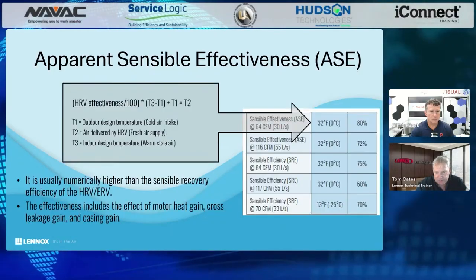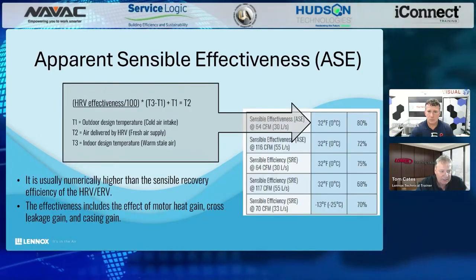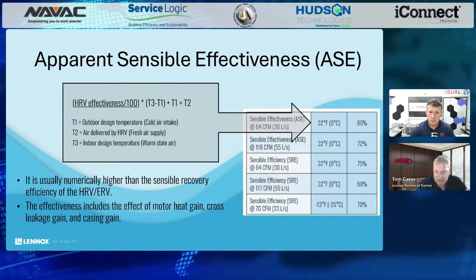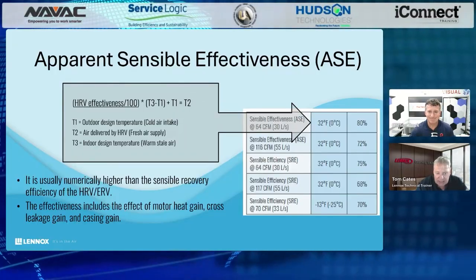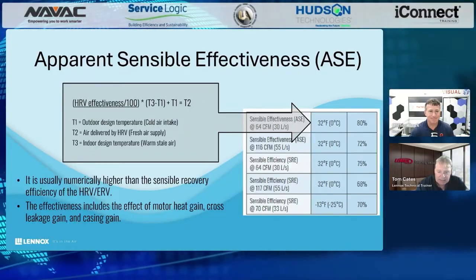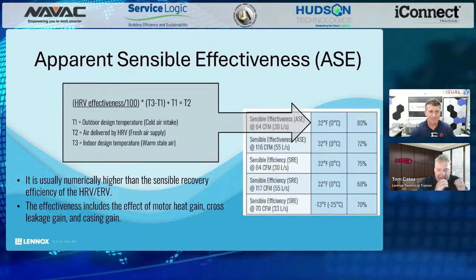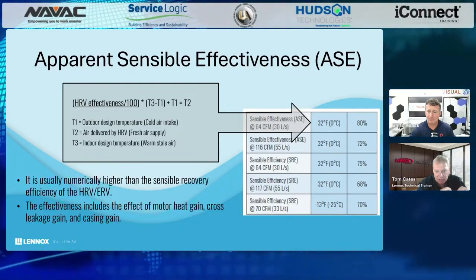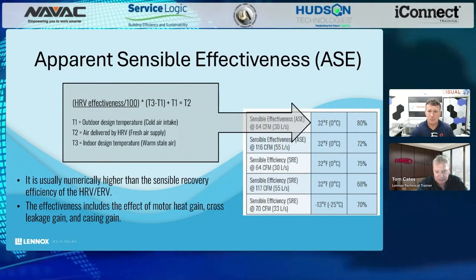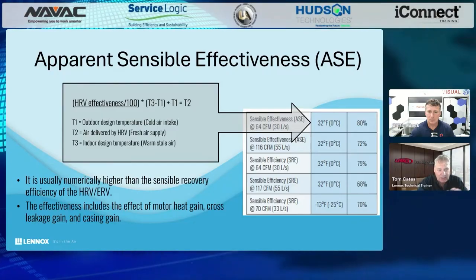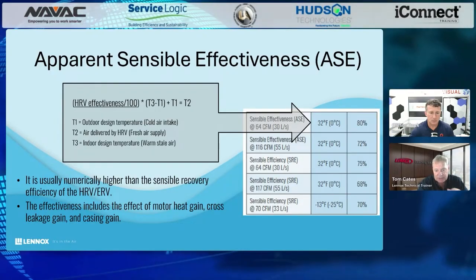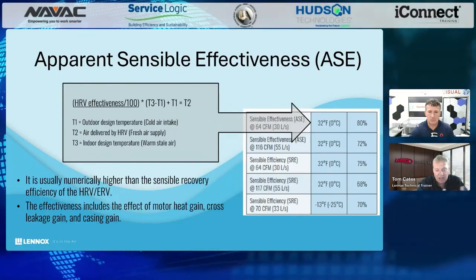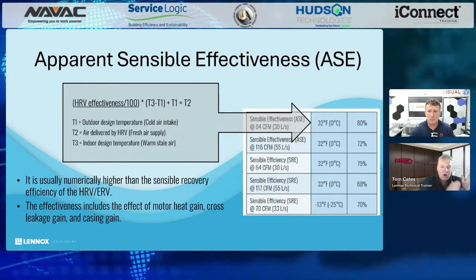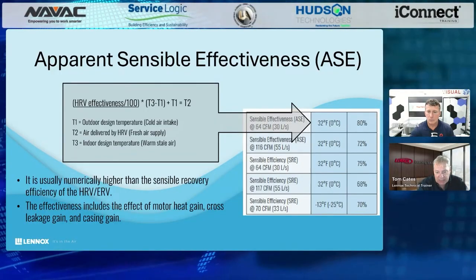The first one here is the apparent sensible effectiveness, or ASE. This is a description of the heat exchanger itself, its ability to transfer heat from one airstream to the other. This apparent sensible effectiveness number is a direct result of how good or how poor your heat exchanger itself is made.